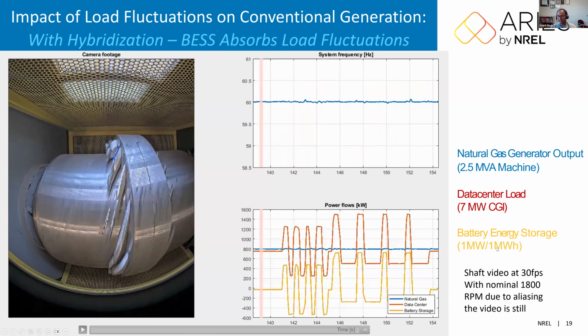Now, in this particular case, we dispatch the battery, using measurement from the load, to absorb all the fluctuations so that the natural gas generator output remains steady and the variations are absorbed by the battery, so that we don't see this impact on the shaft. This was discussed in a previous presentation.